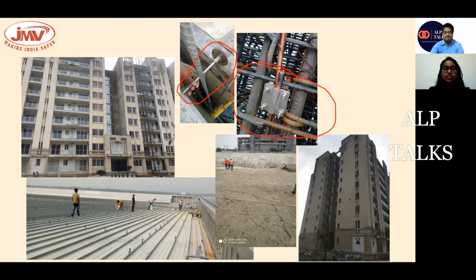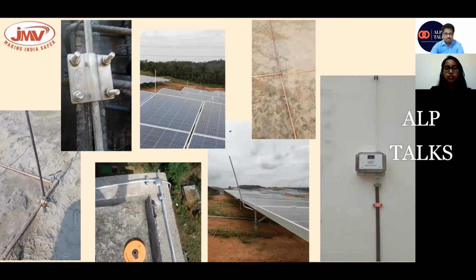So, these are some of the installation images. As you can see, this is the picture from the airport building, because generally airports have sheds. So that is where we lay the conductor. We go for the mesh method plus protection angle, the combination of mesh and protection angle. At every 1 meter, we give the holders.